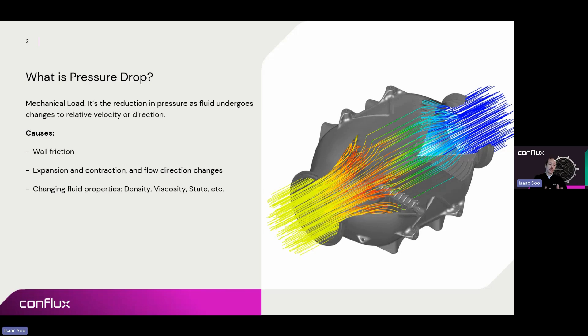But the question is, why does this really matter? In most of our designs, the core is the majority of the pressure drop, with the manifolds also contributing. It matters most because pressure drop fundamentally drives the heat exchanger design: the size, the type, and the layout. So the pressure drop constraints we work within when designing heat exchangers are really important. We're always trying to maximize heat transfer in our devices, but balancing the heat transfer rate against the pressure drop resistance of the system can be a challenge.